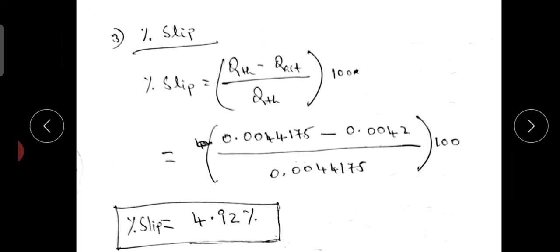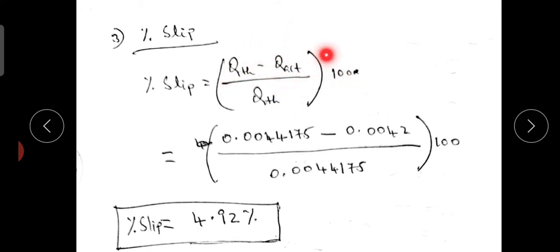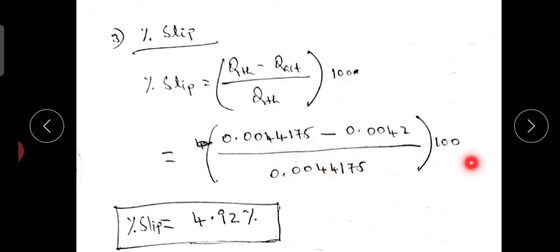Percentage slip: the formula is — theoretical discharge minus actual discharge, divided by theoretical discharge, multiplied by 100. Substituting the theoretical discharge and the actual discharge values, the percentage slip comes to 4.92%.